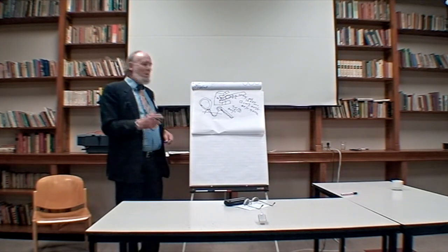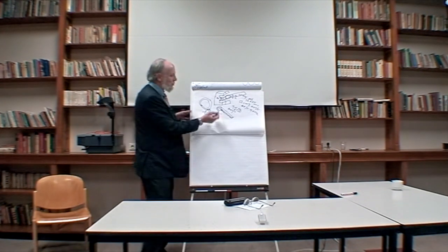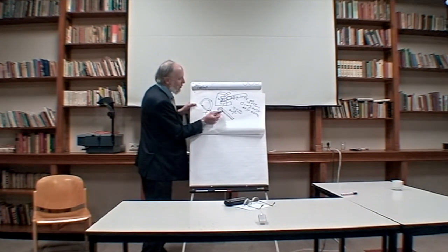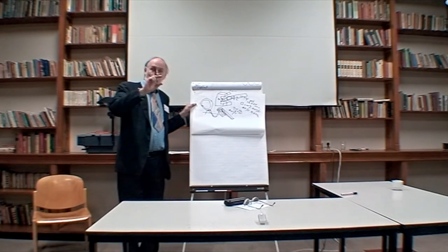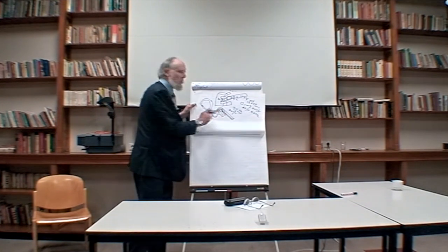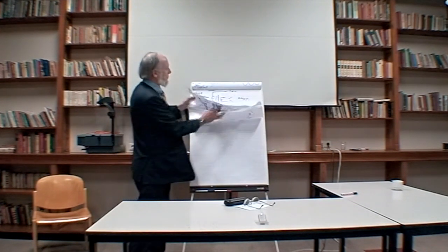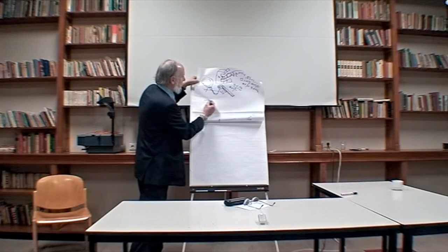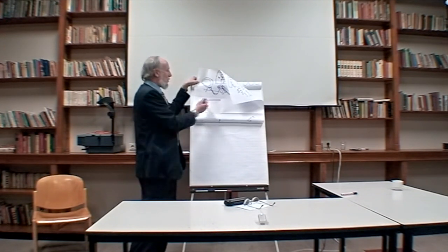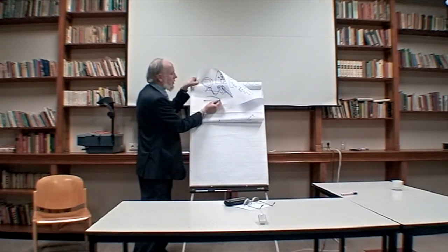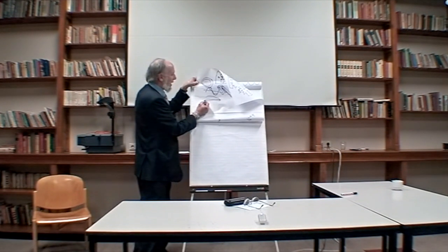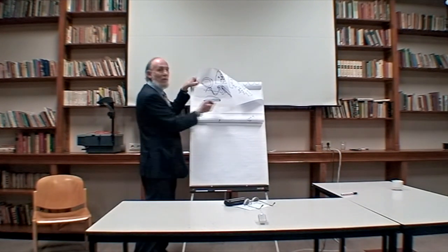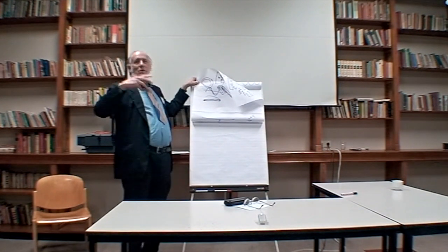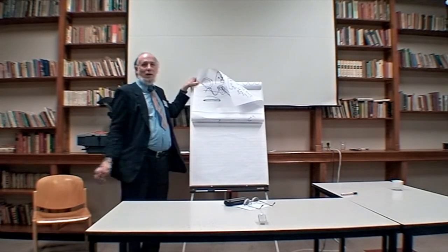Problem with C-cores, you've now got to make bobbins to go on them. The best method, you can design transformers where with two C-cores you have a bobbin on this side and another bobbin on that leg. You've got to make two very small bobbins. If you make it this deep, you now have a bobbin hole where you have to make a mandrel on the winding machine, so the wire is going on and you're trying to make it lay flat, go around the corner, lay flat, go around the corner. So there's this inevitable problem when you go to a very deep stack.